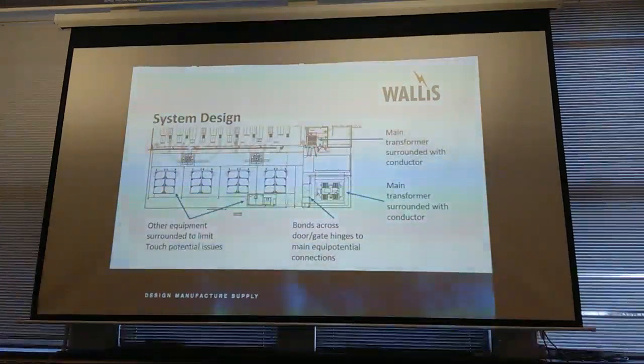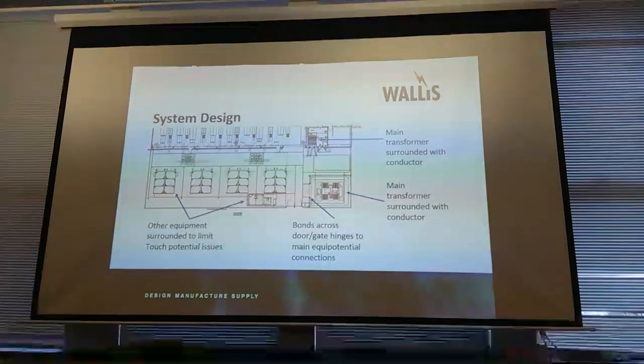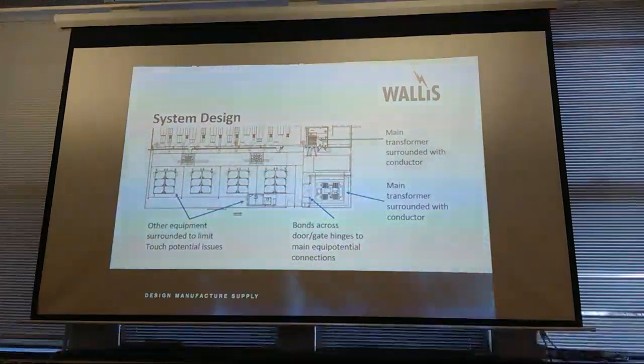This was a little site that we did. I'm sure you guys have come across all these sites that they're shoving in, short-term operating reserve, little gas-fired generator set sites that are being shoved in right up and down the country, because all the coal-fired generating stations are going offline. We need resilience as a country. So what they're doing is finding any old business units, any old industrial units with a decent electricity connection and a decent gas connection, and they will put a series of generator sets in, connect them up to the grid, and as soon as National Grid needs additional power, all they do is dial in and fire these things up. They're going in everywhere.